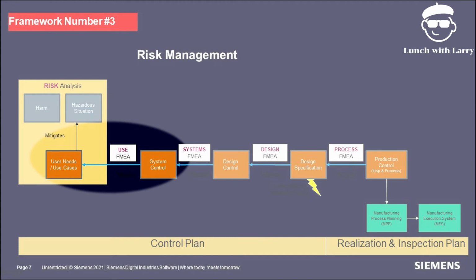And when we do that, we need to be compliant with a certain external standard. The external standard that controls EO sterilization is 11135. So our system control would be that the device will be compliant with the 11135 standard. We believe if we're compliant with the standard, then we're going to have the ability to assure that the user need is met, that the device will be sterile.